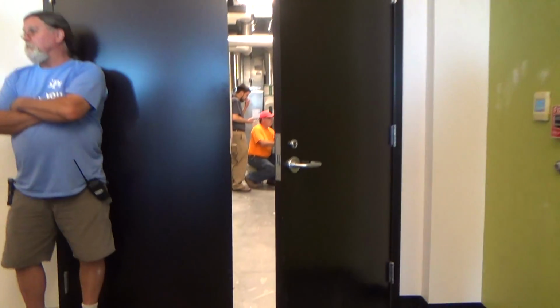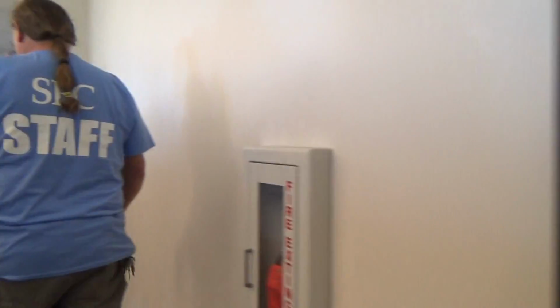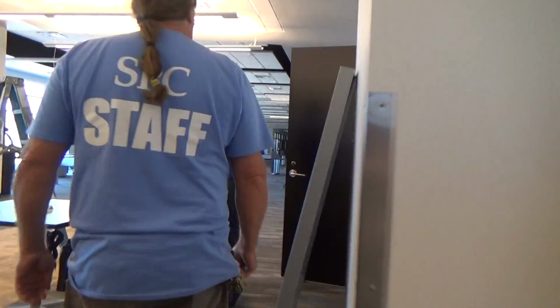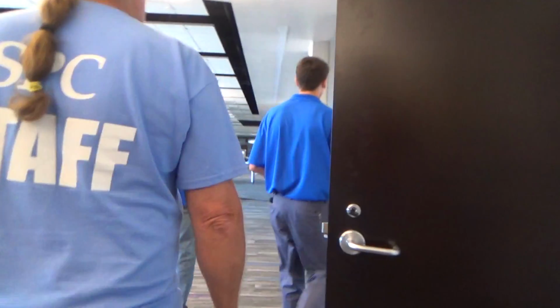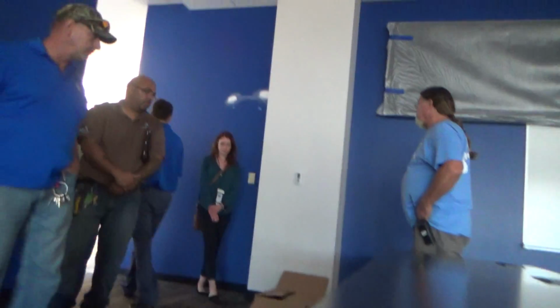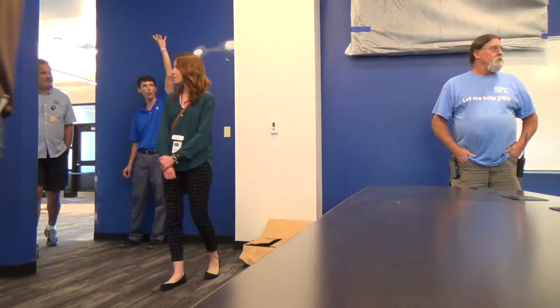We do have some other offices, kind of classrooms up here that I'll show you. I don't think we've seen any of these single pole switches yet. So this is a good example of an area that's going to be manual on. It's a classroom, so people may be walking through here, but really it's not an open area. It's more of a private classroom. So when you walk in, you're going to have to hit the button to turn the lights on, and that's one switch leg, so that's one power pack, and then this other switch is programmed for the other power pack.